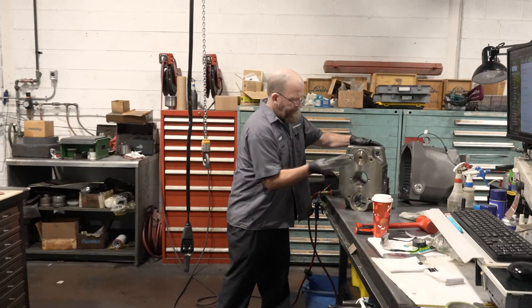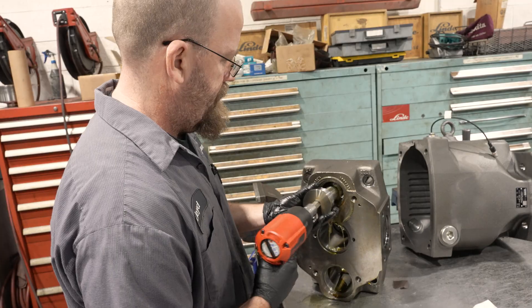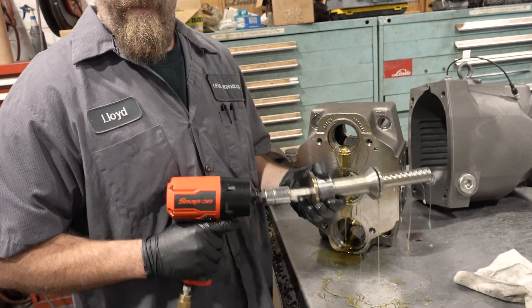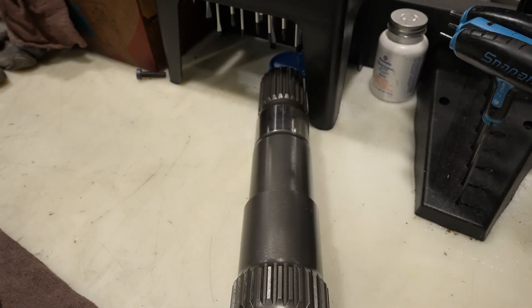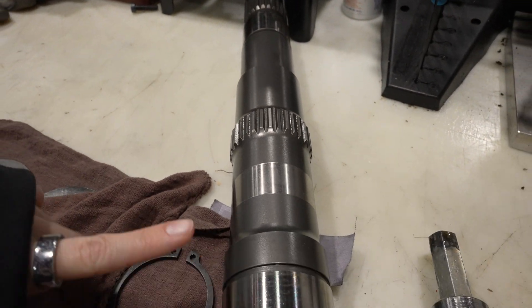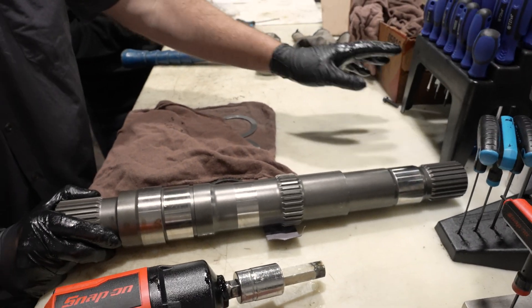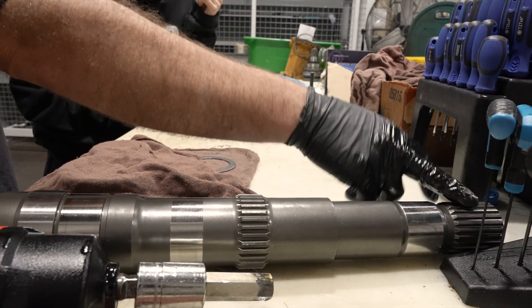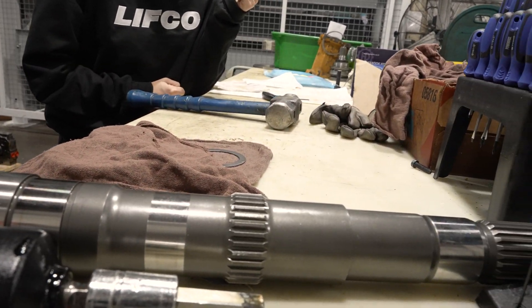It's massive. There's the shaft — it's huge. So there are three splined areas. This first one is your drive that you hook up to your electric motor, diesel engine, or coupler. This middle section is where your barrel sits to drive the rotating group. And this rear drive is to put an auxiliary pump or whatever you want on the back of it.